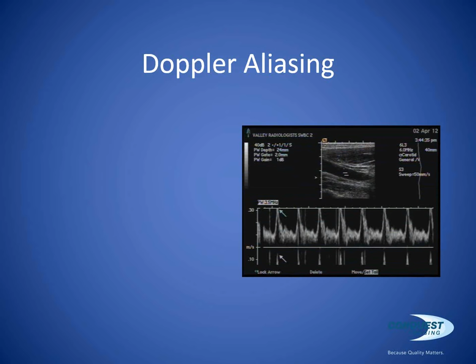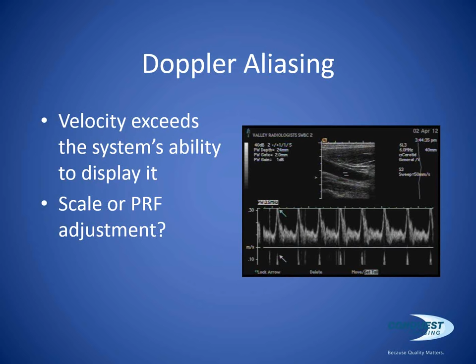If you look to the left of the scale here, you see the numbers 0.30 and 0.10. That is our scale or PRF adjustment. We can adjust that to accommodate the faster Doppler signal. If you look at this image here, you can see that our Doppler signal is going up to the very top of the graph and then wrapping around and coming in from underneath. This shows us that we have the system not adjusted properly, and this is called aliasing. Color Doppler can also alias.